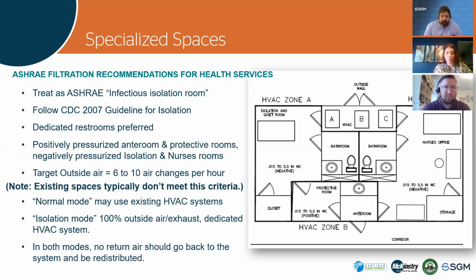And then they should target 6 to 10 air changes per hour. So you're all going to go, wow, that's huge. And most HVAC equipment that's currently in hospitals or nursing stations cannot do that. A lot of these hospitals want to use these rooms in a normal mode until they are forced to make some isolation rooms. So once it goes into an isolation mode, you can look at the picture next to the text there.